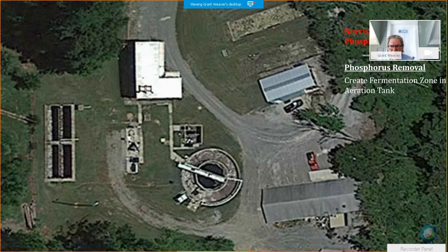Let's divert our influent around the zone. Let's turn the air off on the zone. No, let's divert our return sludge around the zone. I'm sorry, divert the return sludge away from coming in where the influent does. Move it a few feet further into the tank. There was a dividing wall already built in. Of course, the wall had some holes in it, not because of age, but because of design, so the flow could go into that area and then migrate through it into the subsequent area.